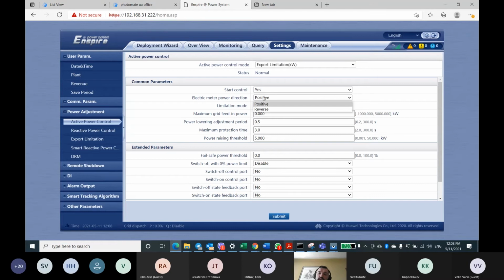But always, please, always, this is a very common mistake: you need to check the correspondence between current circuits and voltage circuits, because very often installers connect, for example, phase A voltage circuits, but put the current transformer from phase B to this circuit. In this case, you see positive values of the energy flow and energy consumed, but it's a completely wrong value, not corresponding with reality.